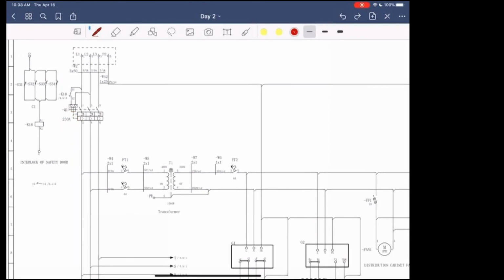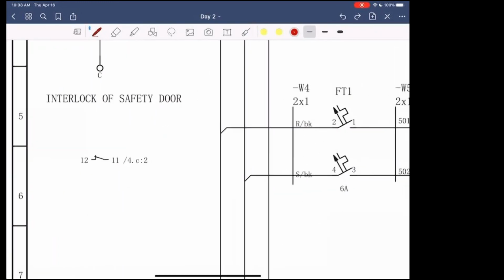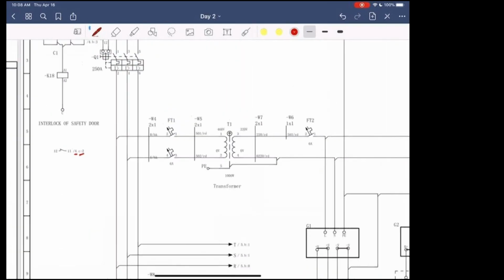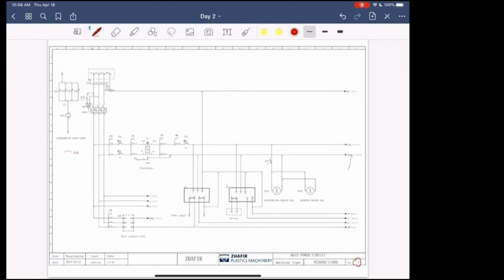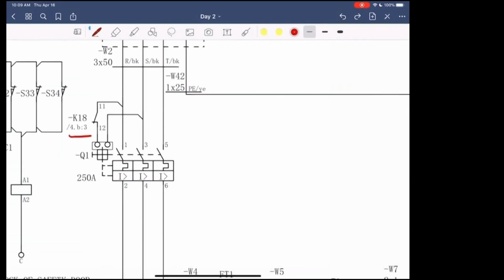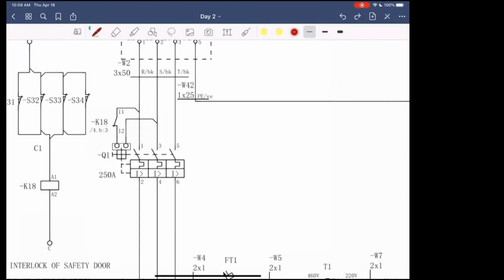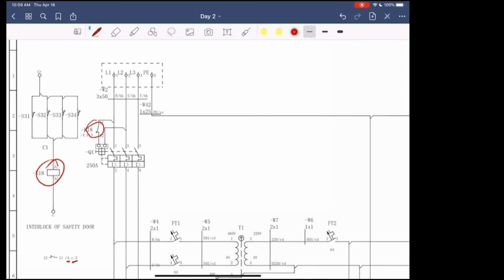And again, I got to show you this because it's a relay, A1, A2, and it's controlling K18. Down here, it shows you the contact for that relay. It's using pins 12 and 11, so it's normally closed. You blow it up a little bit. The location for it is going to be on page 4, C2. Again, we're on page 4. If you go to C2, in this area, of course, it's a little bit C2 in 3/4 maybe, but that's okay. C2 will show you that that's the contact for the K18. So you have the solenoid over here and you have the contact over here.